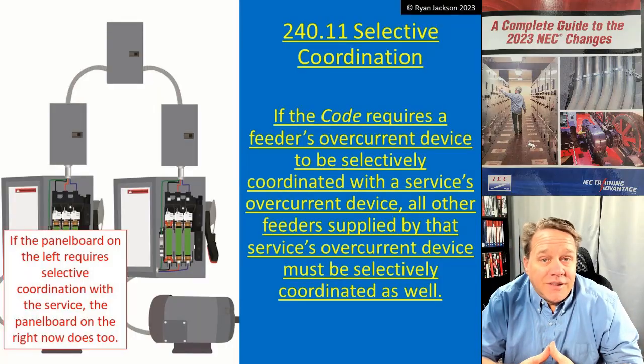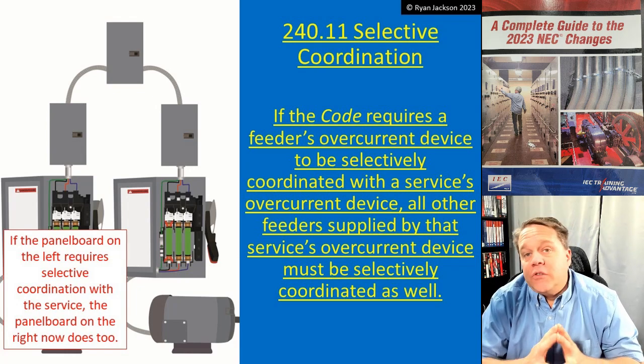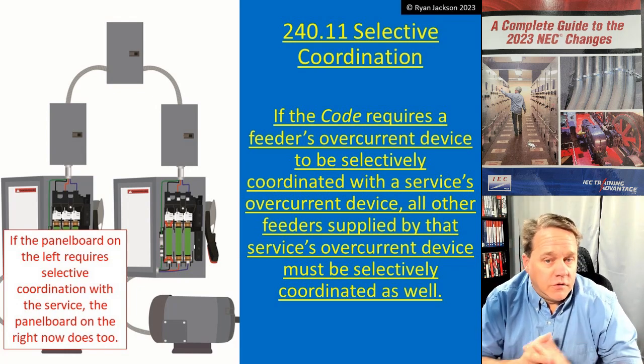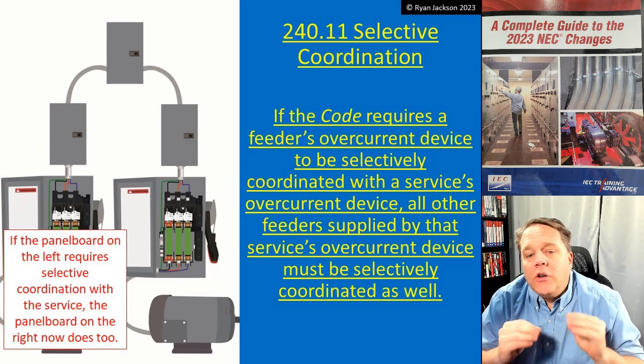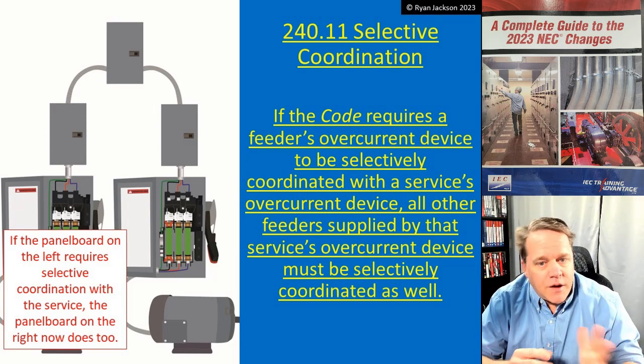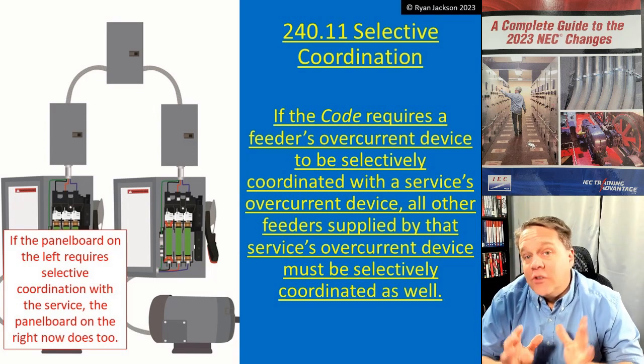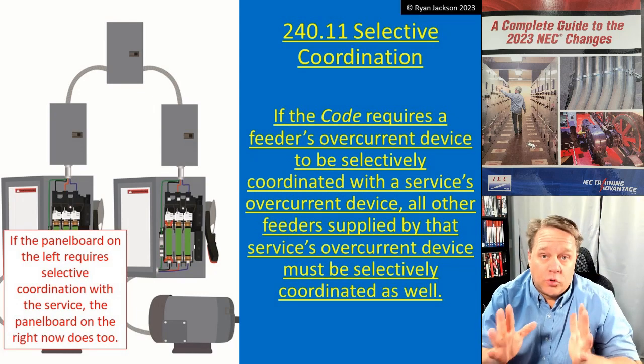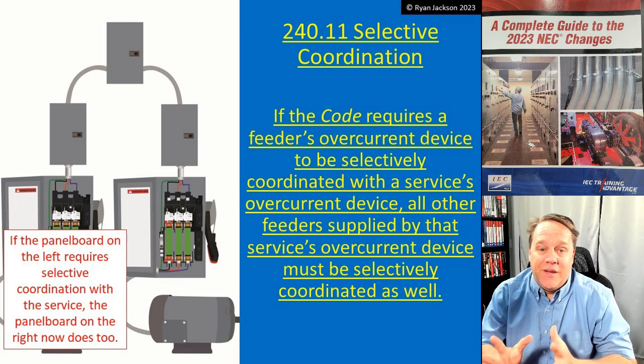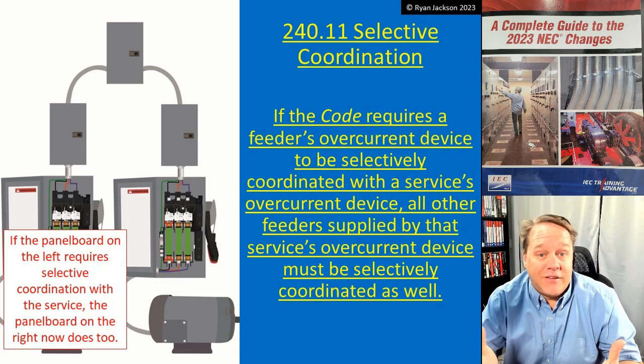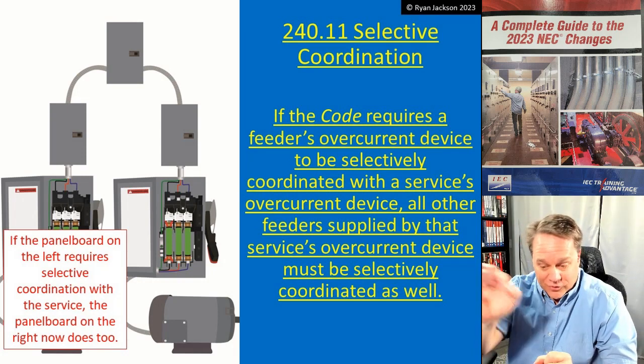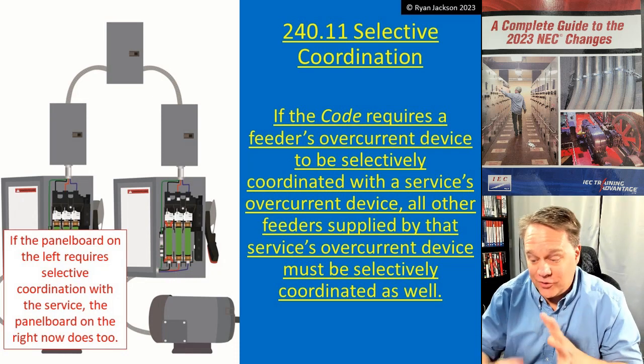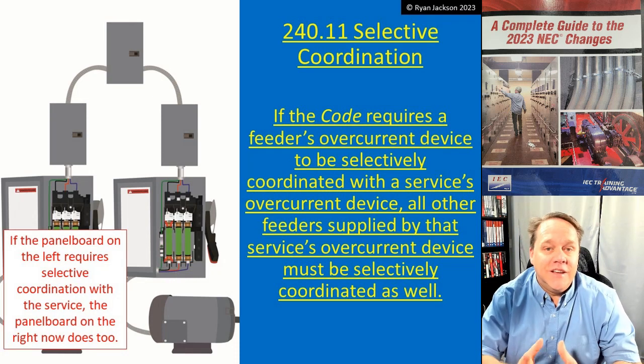240.11 says: if the code requires a feeder's overcurrent device to be selectively coordinated with a service's overcurrent device, then all other feeders supplied by that service's overcurrent device must be selectively coordinated as well. You have to draw this out or it's not going to make sense - hats off to the guys on the code making panel, because writing that in a way that actually makes sense is not easy.